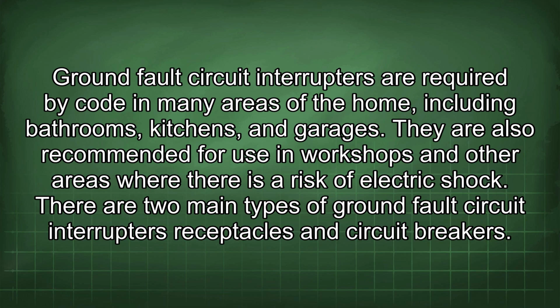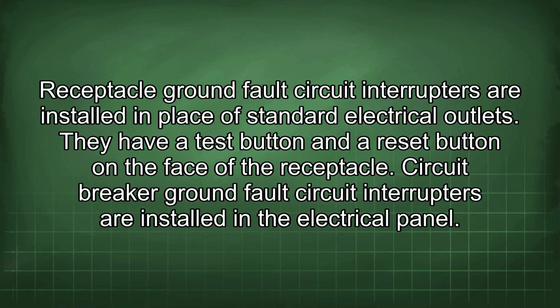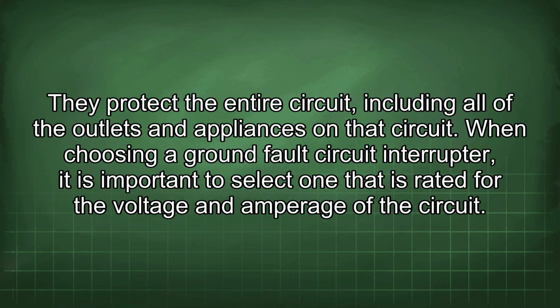There are two main types of ground fault circuit interrupters: receptacles and circuit breakers. Receptacle ground fault circuit interrupters are installed in place of standard electrical outlets. They have a test button and a reset button on the face of the receptacle. Circuit breaker ground fault circuit interrupters are installed in the electrical panel. They protect the entire circuit, including all of the outlets and appliances on that circuit.